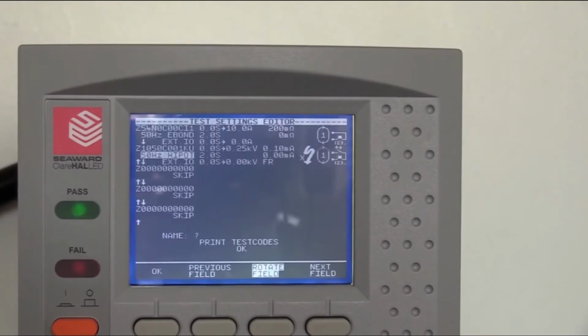In terms of all of the HAL units, we can either do a 50 Hz, a 60 Hz, or a DC Hipot test. So for us, we're going to do a 50 Hz Hipot test. Again, you can see we have times, we have output voltage this time because it is a voltage test. We have limits, we have our front and rear connections. We'll talk about those quickly in a second. Again, the number of times we want to perform the test and any start conditions that we want to set.